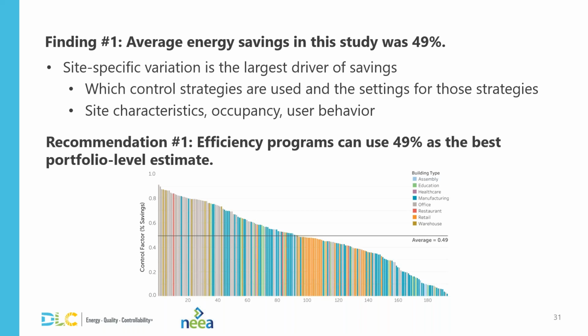Visual analysis of load profiles during the quality control process suggested that many sites with lower savings are simply using NLC as a zone-level scheduling control with HighEnd Trim and not implementing the other control strategies. There is likely significant differentiation in occupancy timeouts or settings such as auto on versus manual on. Other major factors that impact the energy savings are the amount of available daylight, occupancy patterns, and individual users' tendencies to turn off the lights when not present.